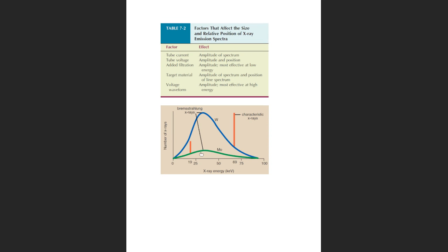It doesn't mean that they won't affect the y-axis. It just means that they'll affect the x as well. So we have kVp, generator phase, filtration. Target material is just discrete only because it'll only happen at a specific time at a specific energy.